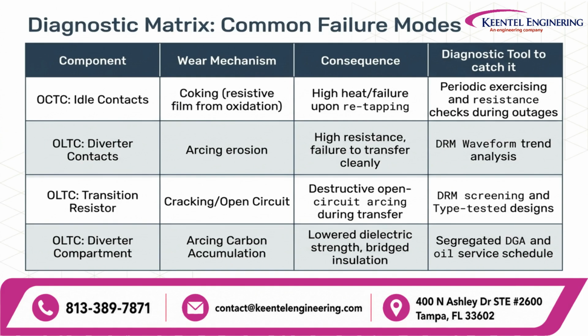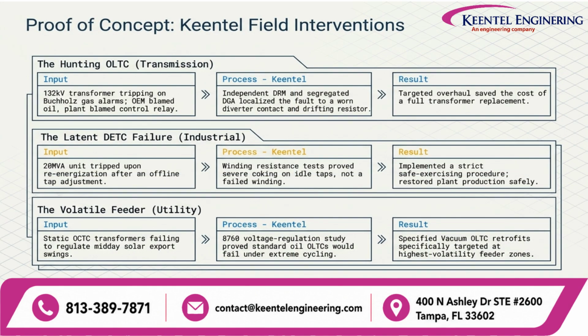Transition resistors may overheat or crack after years of operation. The diverter switch experiences both electrical and mechanical wear because it performs the actual switching process. Motor drives may develop lubrication issues, gearbox wear, or electrical faults. Understanding the relationship between component failures, observed symptoms, and diagnostic techniques enables engineers to quickly identify root causes and implement targeted maintenance strategies. These case studies demonstrate how engineering diagnostics translate into practical field results.